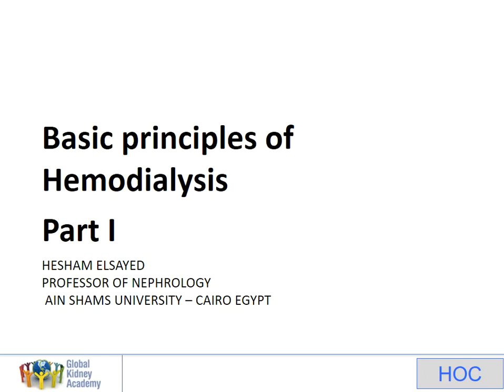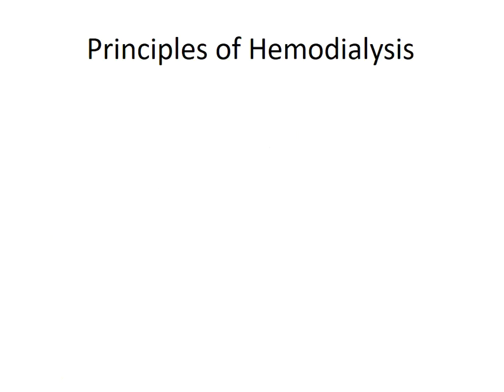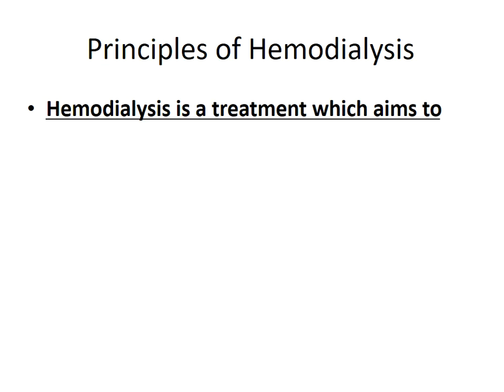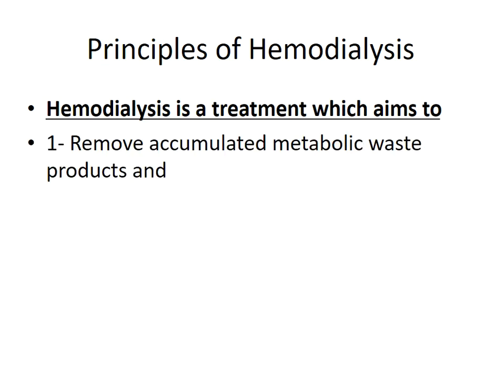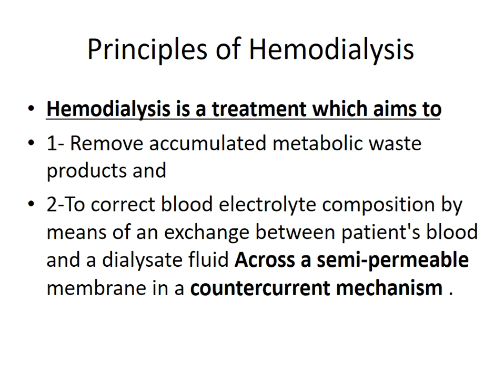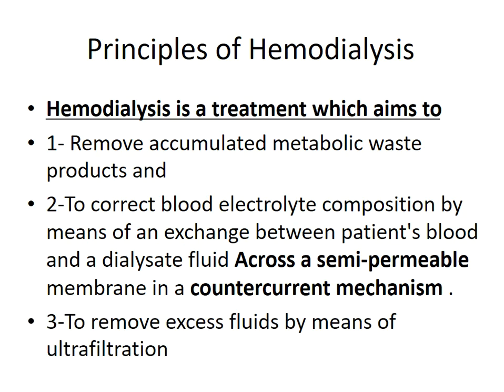This is the basic principles of hemodialysis, divided into two parts. In part one, the principles of hemodialysis: hemodialysis is a treatment which aims to remove accumulated metabolic waste products, to correct the blood electrolyte composition by means of an exchange between the patient's blood and a dialysate fluid that happens through a semi-permeable dialysis membrane, in a flow pattern called a counter-current mechanism. Also, to remove excess fluids by means of ultrafiltration.